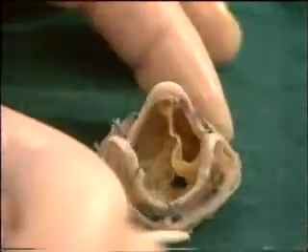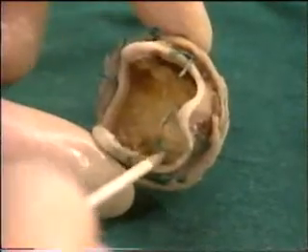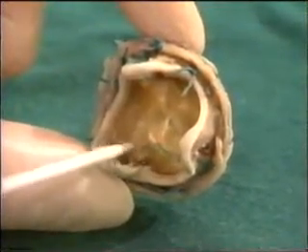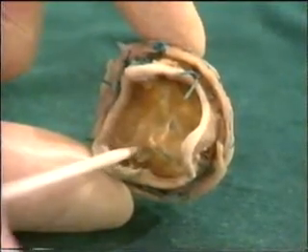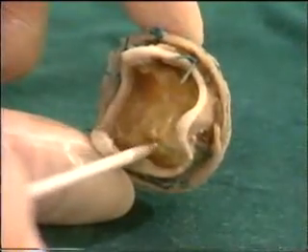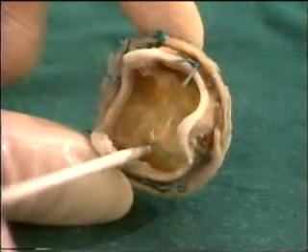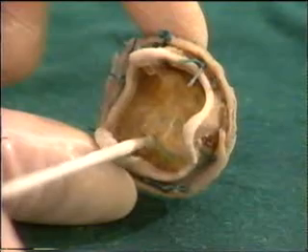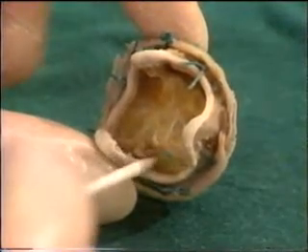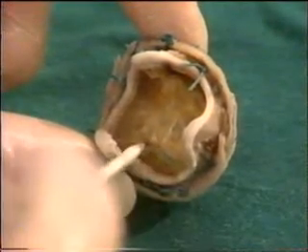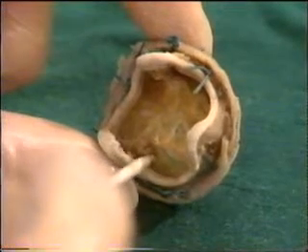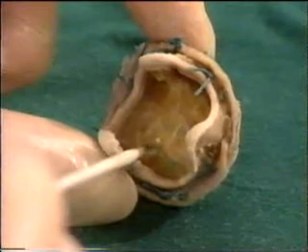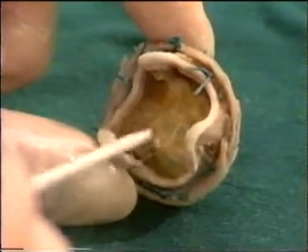We have another bioprosthesis here where you can see a small calcific deposit at this commissure, and right next to it there is a tear, which I'm pointing at now. We generally call the process wear and tear, and the average life of a bioprosthesis is said to be between 10 and 12 years.